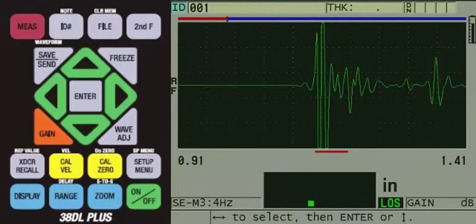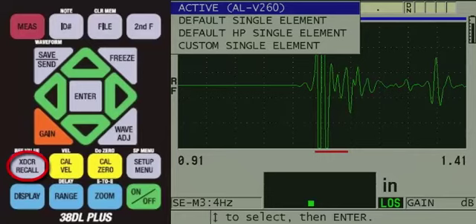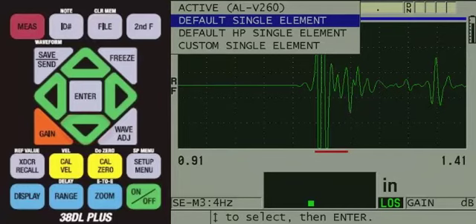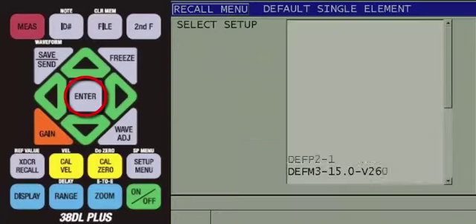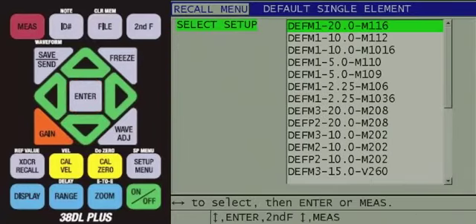The first step would be to press the XDCR recall key. Since we are using a 15 MHz transducer, we will press the down arrow to default single element and then press Enter. Here, you will see the list of default single element transducer setups. Since plastic does not produce strong multiples, we will be unable to make a Mode 3 measurement and will therefore want to make a Mode 2 measurement.